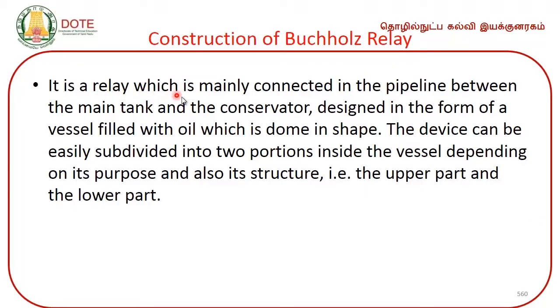It is a relay which is mainly connected in the pipeline between the main tank and the conservator, designed in the form of a vessel filled with oil which is dome in shape. The device can be easily subdivided into two portions inside the vessel depending on its purpose and also its structure, that is the upper part and the lower part.